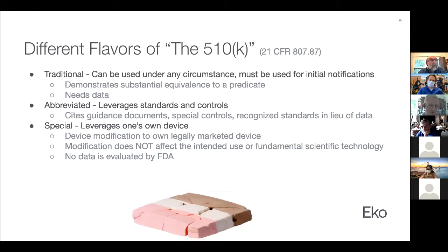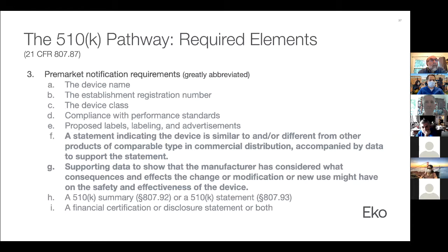This is a slide for your reference, in that there are different ways to get marketing clearance in the 510K. I'm going to just skip over that to keep moving. 807.87 is the laundry list of things you need to produce in a marketing application. I'm just going to focus your attention on F and G. You need to provide a statement that says the device is similar to, or how it's different from, a device of comparable type that's already in commercial distribution.